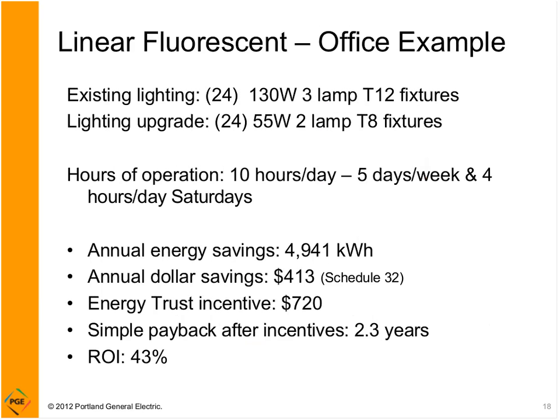So the annual energy savings, you're getting close to almost 5,000 kilowatt hours a year. A dollar savings, about $413. The energy trust incentive that comes into play would be about $720. So a simple payback after incentives, 2.3 years, and return on investment, 43%. So very cost effective, good investment, good project.